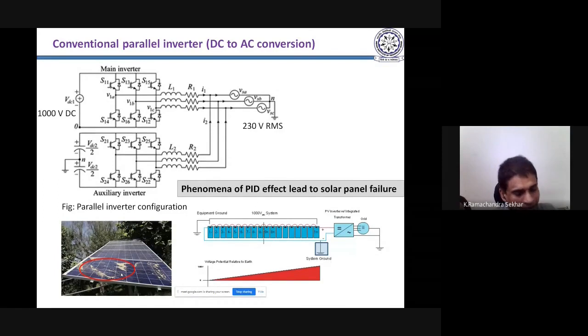Yes, we have seen this many times. Even if you go to a solar panel and put a clamp meter at the ground terminal, ideally no current should flow because it's all isolated and there's no potential at the frame. Only during lightning and such, some current might flow, but ideally no current should flow. But if you put the clamp meter, you will always see some current. That means it's a leakage current.